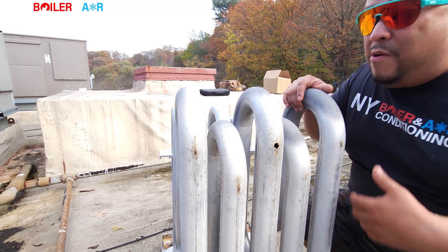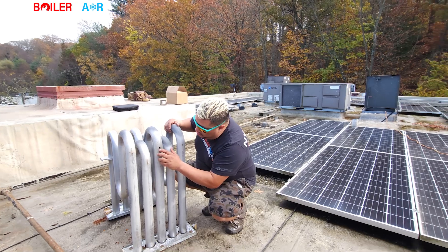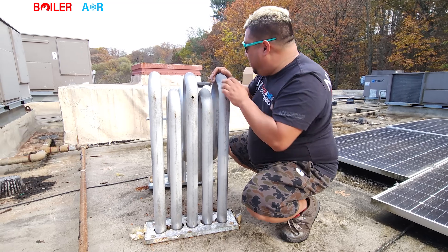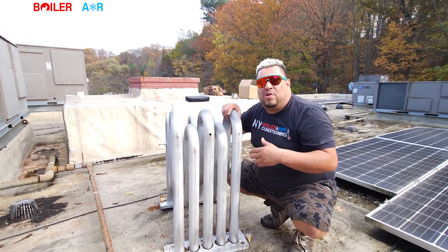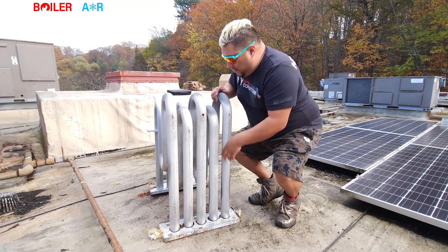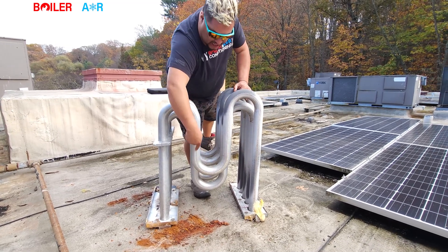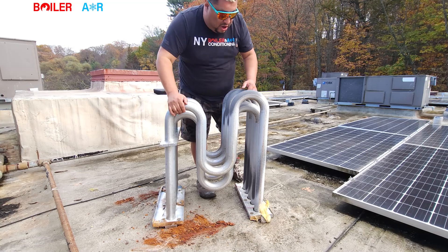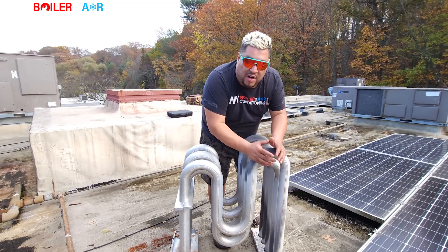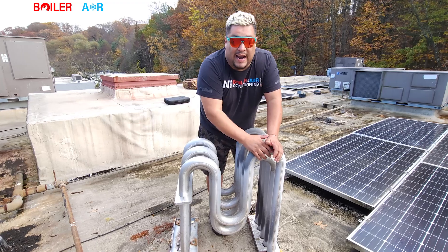People that are working in the office, you do not want to get the space contaminated with carbon monoxide. So this is super important, guys. This is leaking from the bottom, there's another one here — the pinhole. This one's about to start. Typically when you get these holes or pinholes, they usually start on the first pass. So when we see these heat exchangers, look on the side — this is called pass one, pass two, pass three. On the first pass, typically that's the one that gets the damage, because it gets the brunt of the heat from the actual flame or the gas valve.